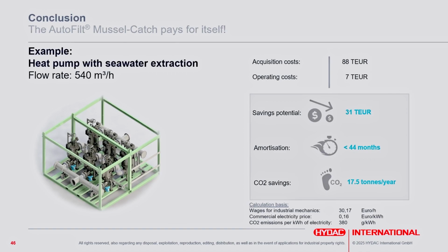The acquisition costs of only the fine line, since the coarse line is always needed for the heat exchanger, we only looked at the upgrade, the fine line, were 88,000 euros, and the operating costs were 7,000 euros. The saving potentials mainly come from reducing power due to reduced dP, improving the heat exchanger performance of the plate heat exchanger, and preventing at least one revision of the plate heat exchanger. For these 3 reasons, there's a saving potential of 31,000 euros, meaning the solution pays for itself within 44 months.